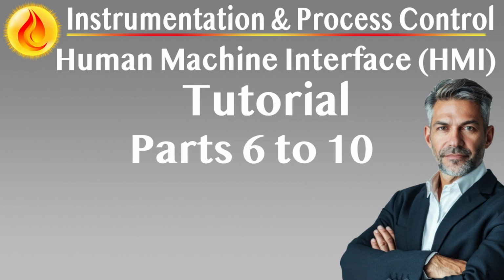Pumps: running equals filled, off equals hollow, tripped, blinking red, fault equals magenta border. Motors follow the same visual behavior as pumps. Manual switches, static shapes unless shown for specific operations. Bad values displayed in magenta with coded prefixes. F equals fault, L equals last value, U equals unavailable. Symbols should maintain a minimum height of 5 to 6 millimeters for visibility from a distance. Labels, e.g. P101A, must be consistently placed, preferably below or adjacent to the symbol, and should never be vertically oriented.